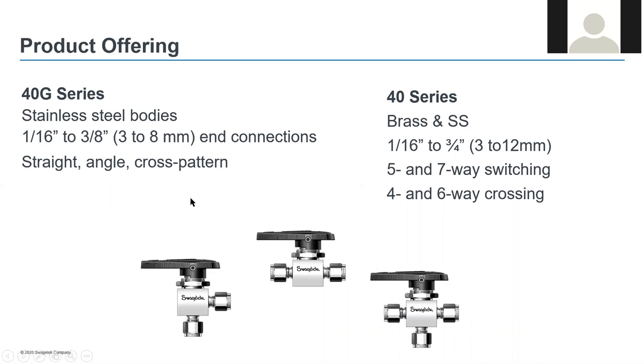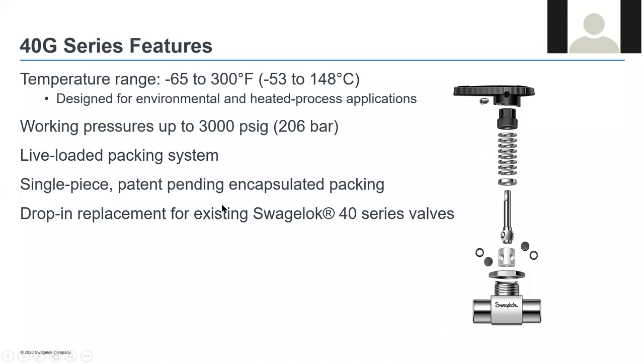The Swagelok 40G series is a one-piece instrumentation ball valve and an evolutionary change to the 40 series line. It combines the proven features of the 40 series and the standard live-loaded T-valve with an innovative seal design that performs in both environmental and heated process applications. The 40G series valve line encompasses stainless steel bodies from one-sixteenth of an inch up to three-eighths of an inch, along with straight, angle, and cross pattern configurations. Working pressure is up to 3,000 PSIG.